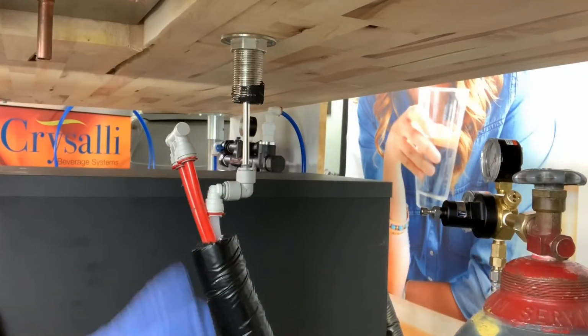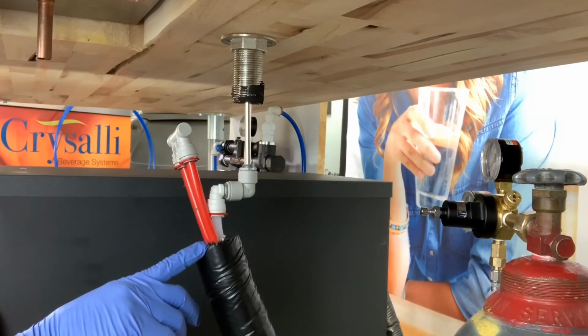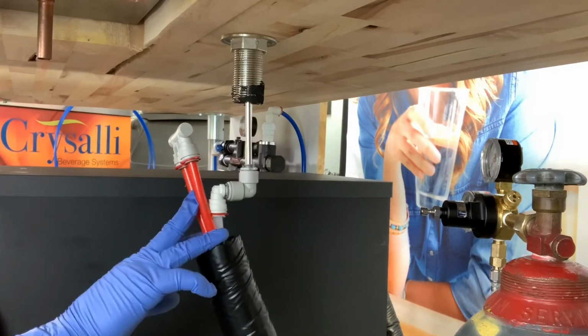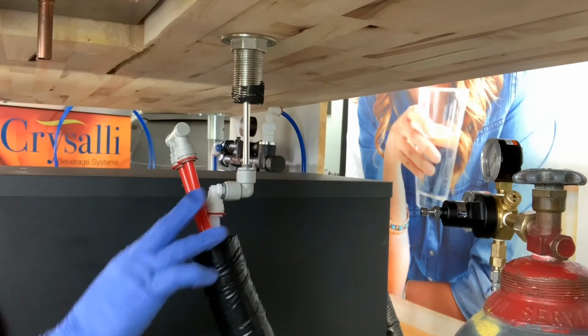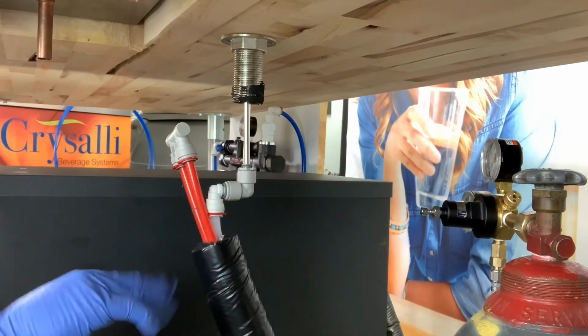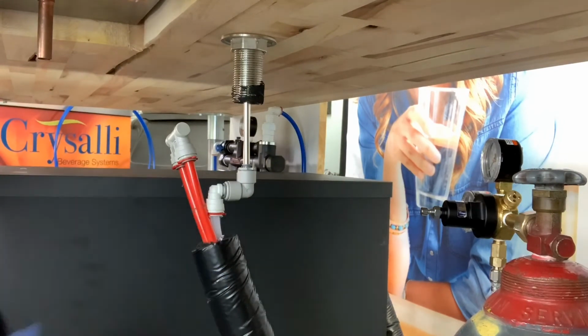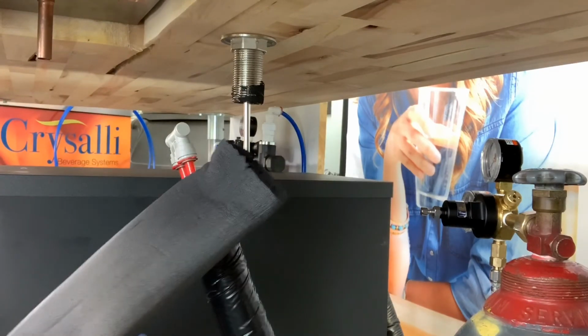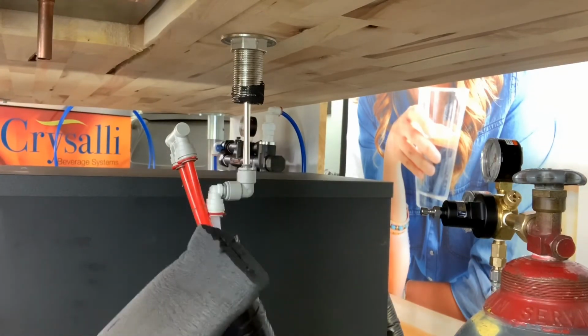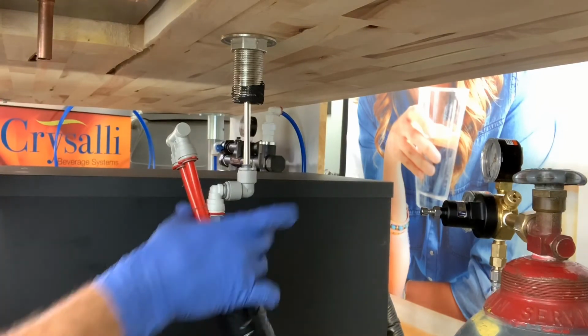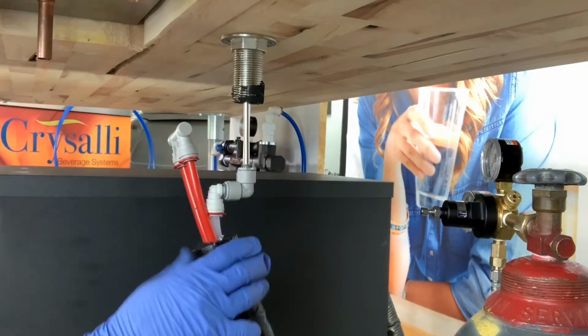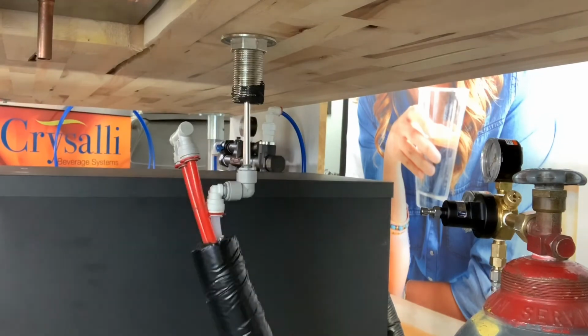Prior to insulating all the lines, I've pressure checked all the fitting connections to make sure there are no leaks. Now that's confirmed, we're going to take the insulation tape and the insulation that comes with the install kit, and completely cover all the exposed lines so you don't get any condensation.